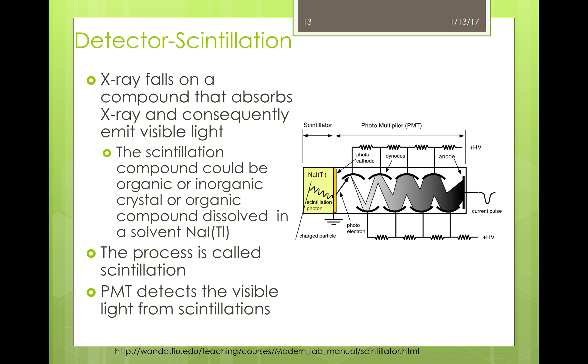During the actual detection, the X-rays are absorbed by a compound that then emits visible light. This process of converting X-rays to visible light is called scintillation. The scintillation compound can be an organic or inorganic crystal, or an organic compound dissolved in a solvent such as sodium iodide activated with thallium. A photomultiplier is used to detect the visible light from the scintillations. The photomultiplier detects photons and then produces a proportional electrical voltage, which is the actual source used by the computer to create your output.